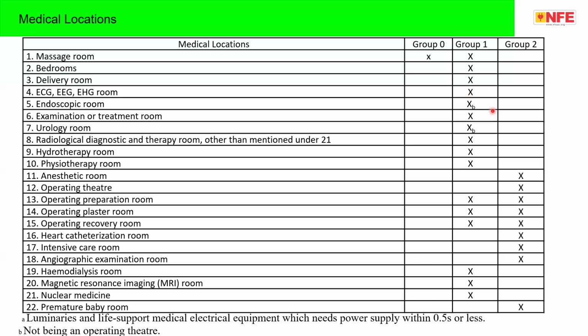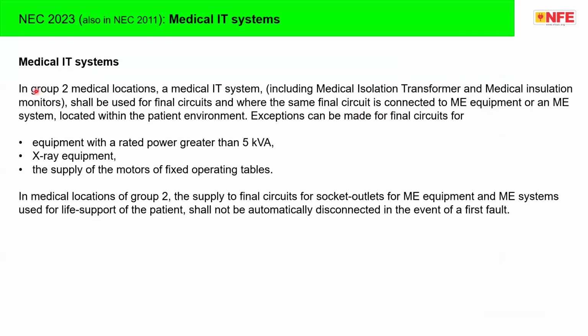I have shown in the standard the single fault condition in the IS standard. Single fault condition means the equipment is faulty or there is some fault somewhere in the installation. The single fault should not cause disconnection. The process should continue. That is the basic. For example, in group 2 location, a medical IT system is required. Medical IT system means a power supply which ensures that even in case of a single fault, your device need not trip. So that is how it is.